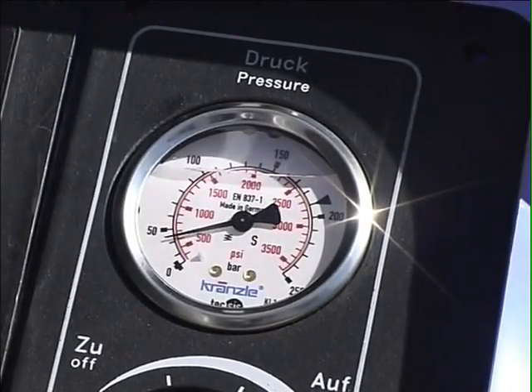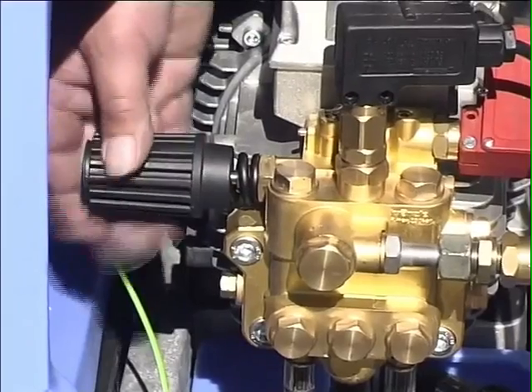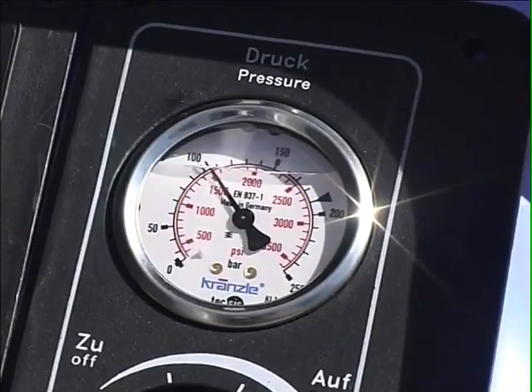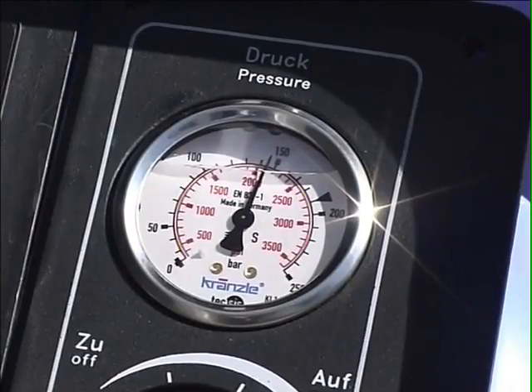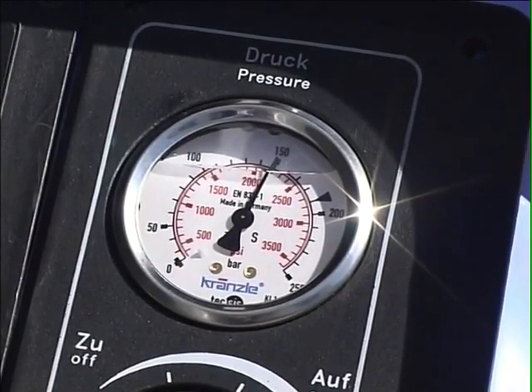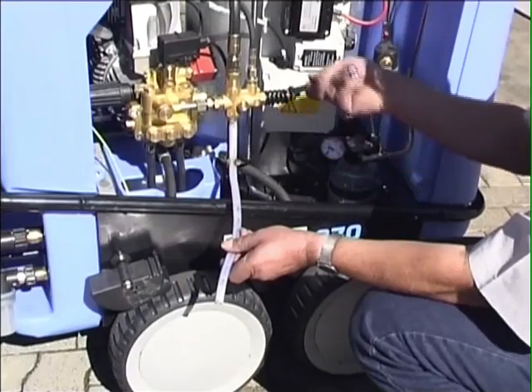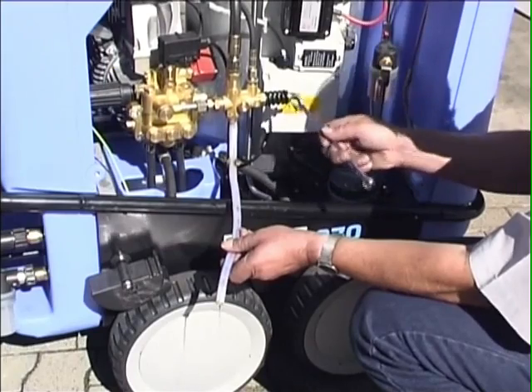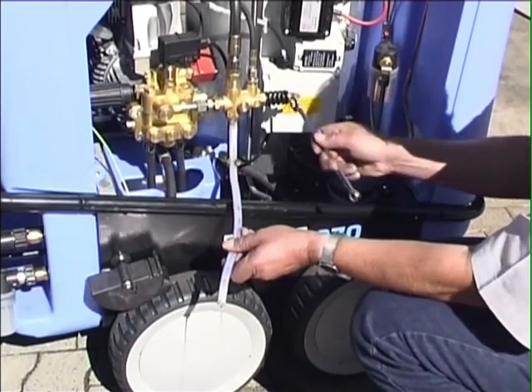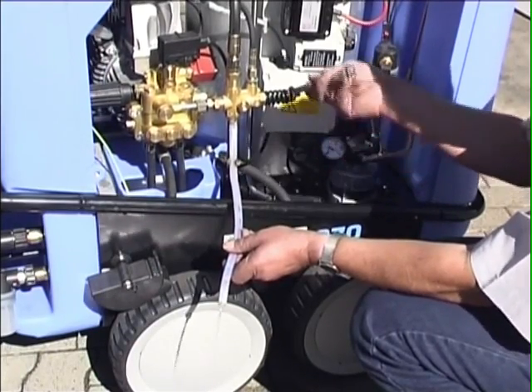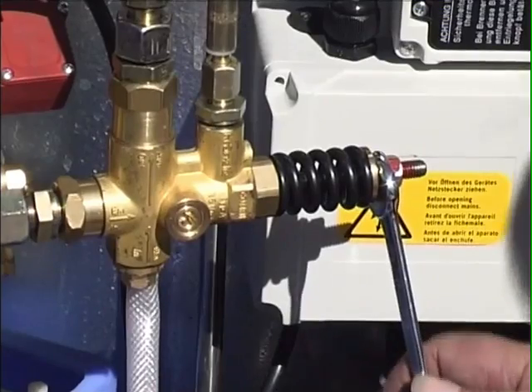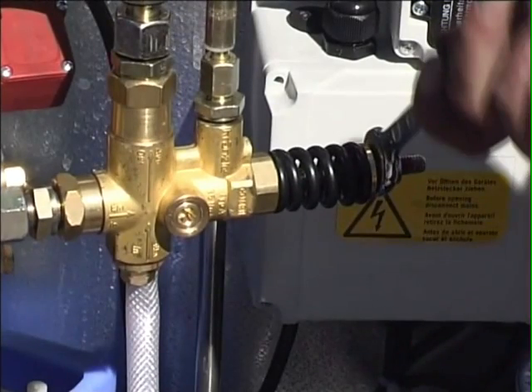After installing the motor pump unit, check the individual functions. After resetting the maximum pressure as set at the factory, the safety valve for the heating coil can be set. You must first reduce pressure on the safety valve until water comes out. Clamp spring until no water pours out any longer. Then turn approximately 1.5 revolutions further to be 10% above the respective cutout pressure of the pump.